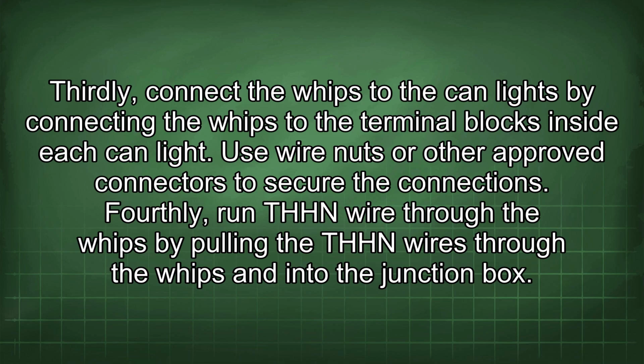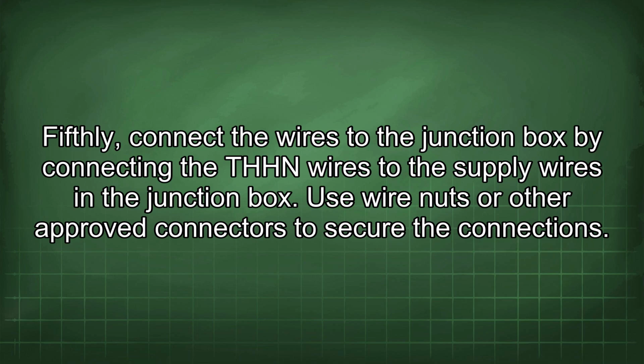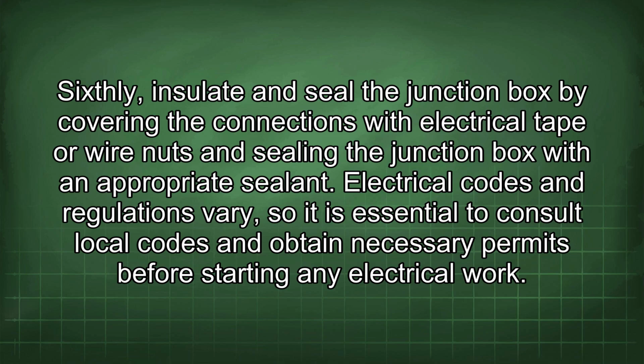Fourthly, run THHN wire through the whips by pulling the THHN wires through the whips and into the junction box. Fifthly, connect the wires to the junction box by connecting the THHN wires to the supply wires in the junction box. Use wire nuts or other approved connectors to secure the connections. Sixthly, insulate and seal the junction box by covering the connections with electrical tape or wire nuts and sealing the junction box with an appropriate sealant.